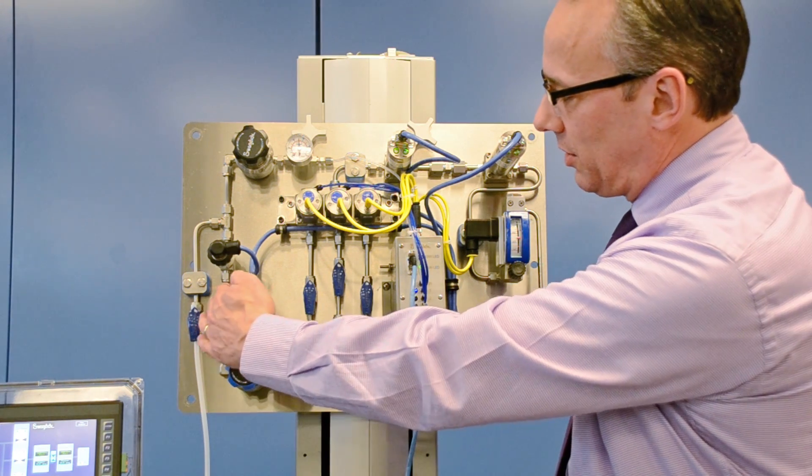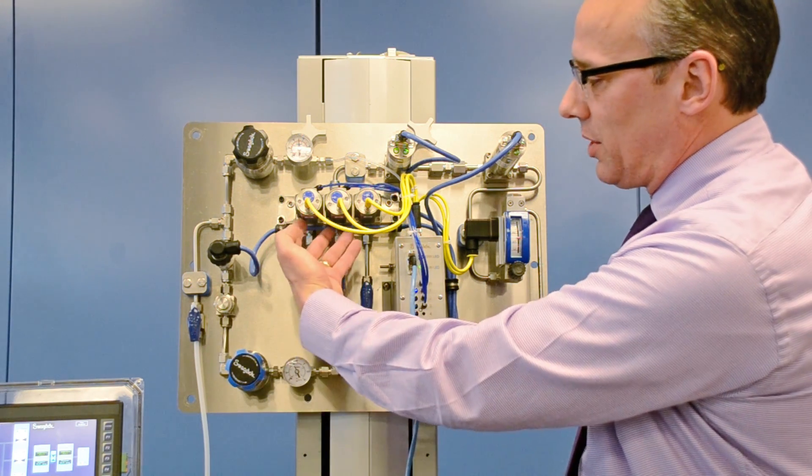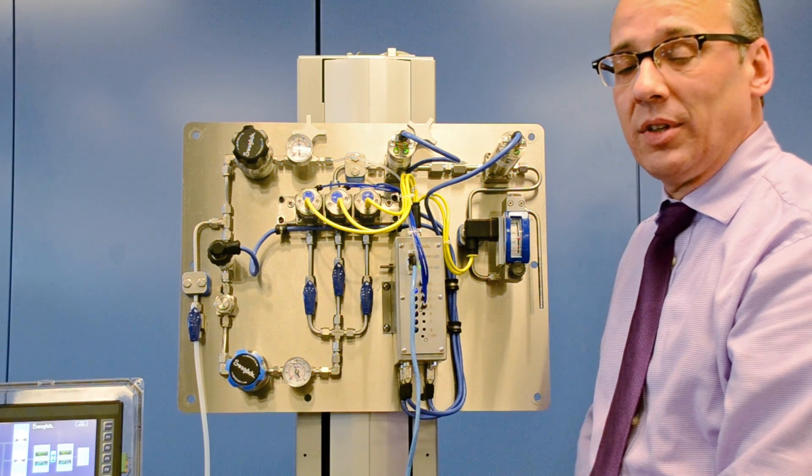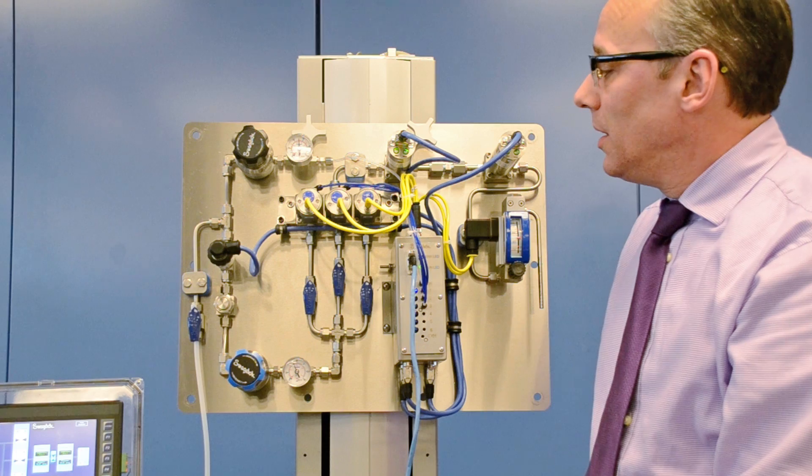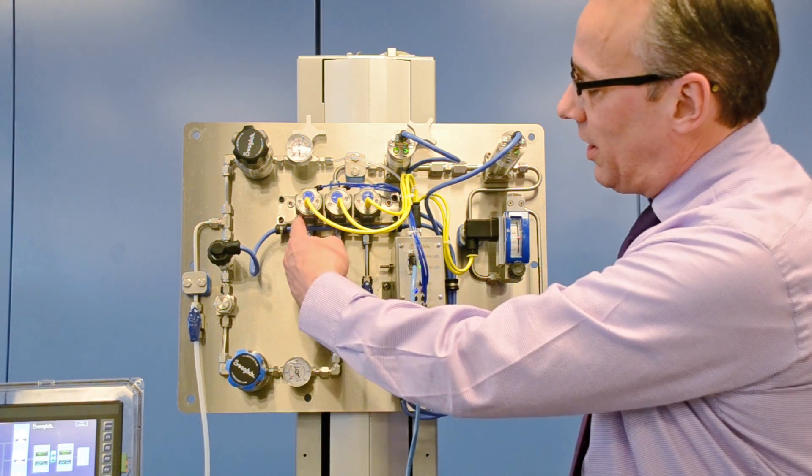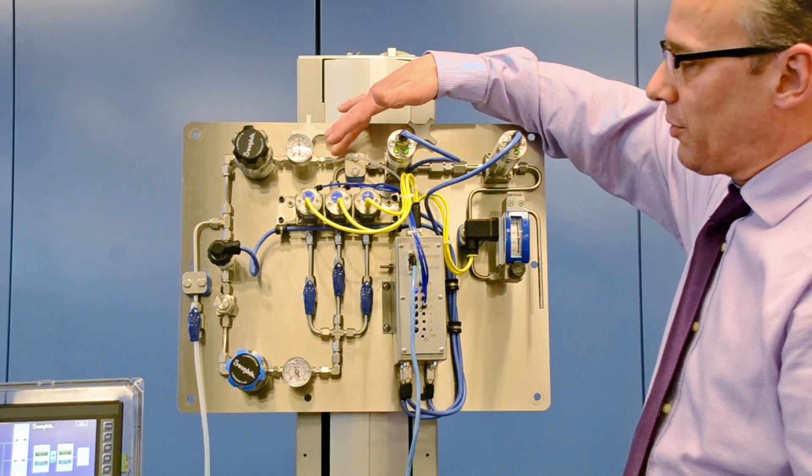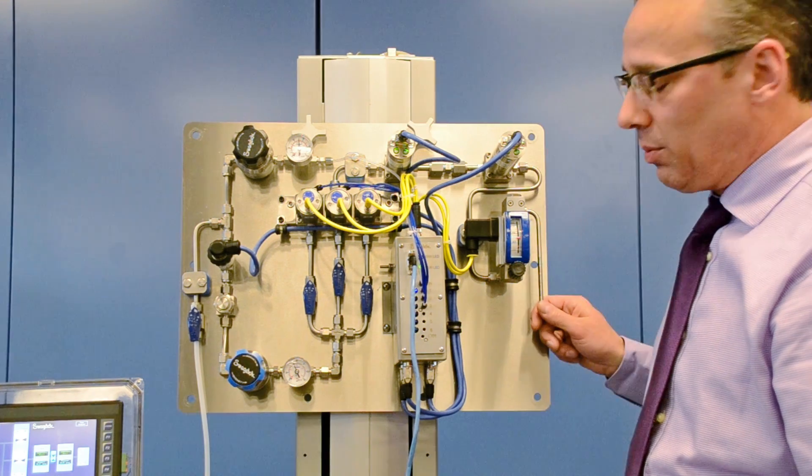As the stream comes in through this system it ultimately makes its way up to this bank of valves that we call the Swagelok stream selector valves or SSVs. Opening one of these valves will allow one of these process streams to ultimately flow through the system and make its way to the analyzer.